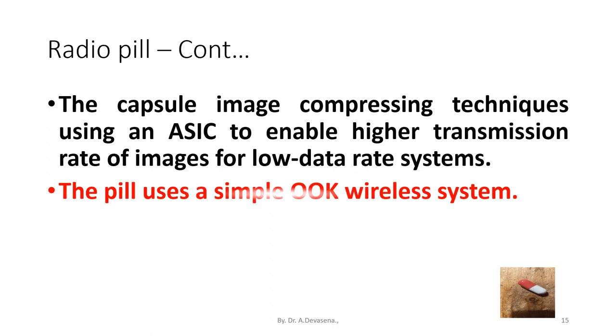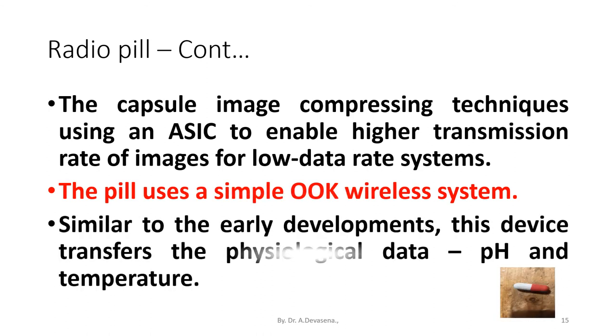The capsule image compressing technique uses an ASIC to enable higher transmission rates of images for low data rate systems. The pill uses a simple OOK wireless system. Similar to early developments, this device transfers physiological data such as pH and temperature.